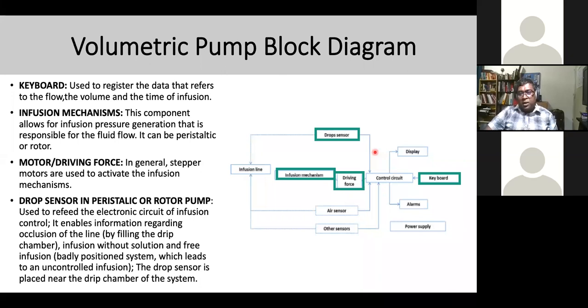Infusion mechanism is one of the most important components for rotor or syringe pumps. It is responsible for the fluid flow, so it can be a peristaltic or rotor type pump. So it manages your fluid flow, all that. This is where the infusion mechanism plays a key role. And the motor driver, generally they use a stepper motor, used to activate the infusion mechanism base. It activates the movement of the mechanism itself.